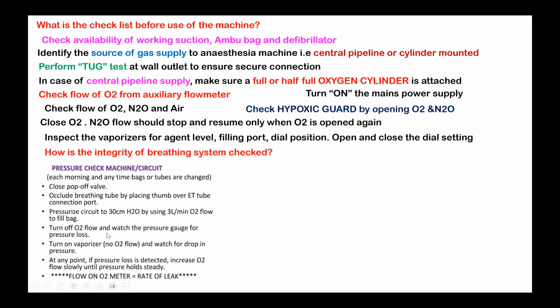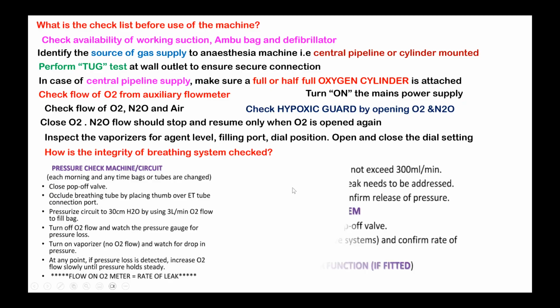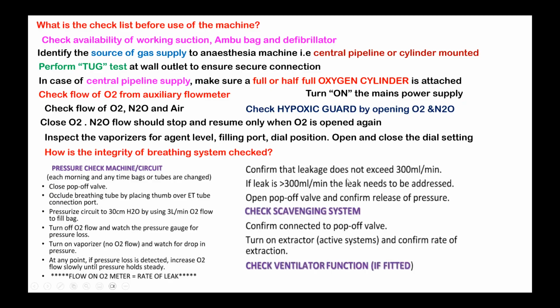Then switch off the oxygen flow. Watch the pressure gauge for any pressure loss. Then turn the vaporizer on, with the oxygen still closed, and watch for any drop in the pressure. At any point, if pressure is lost, that means there is a leak inside. Then confirm that the leak does not exceed 300 milliliters per minute. Okay? And check scavenging systems, check ventilation function.